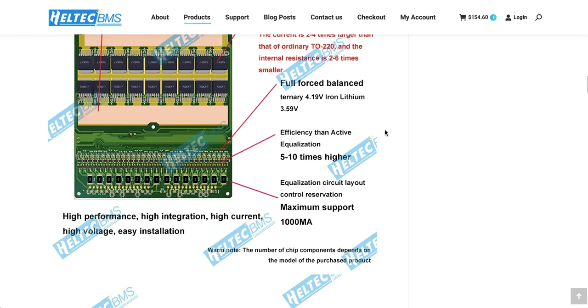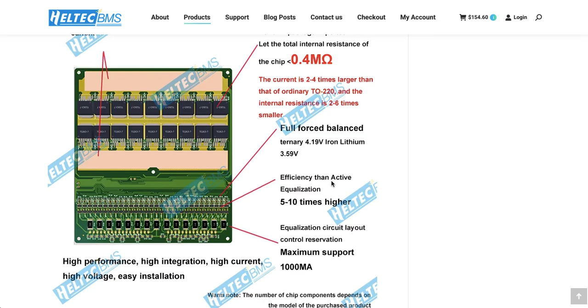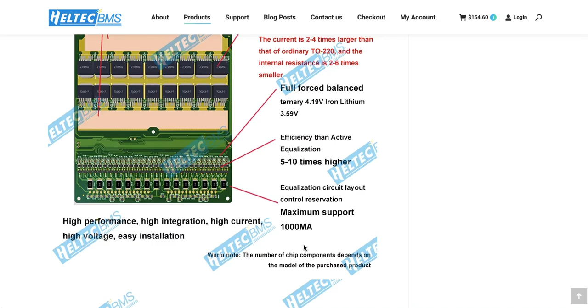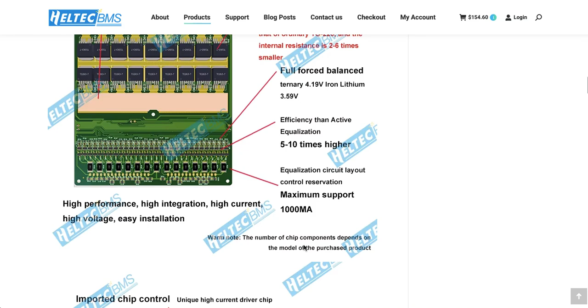I don't really know - I guess efficiency is 5 times higher than active equalization, or it's using active equalization. But you get up to 1 amp balancing. That's pretty sweet. So if you had a weak cell, it could keep up with everything because it could get up to 1 amp charge balance or discharge.